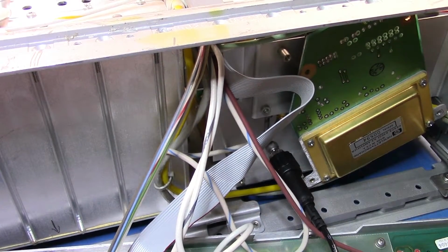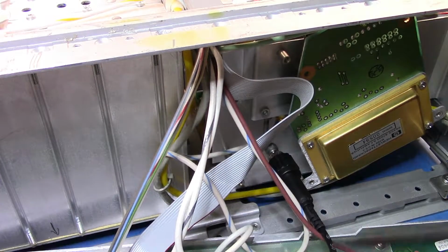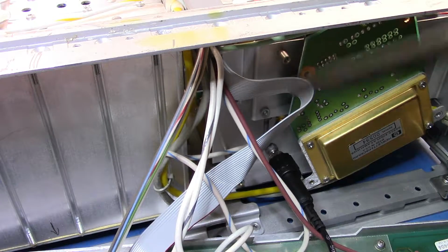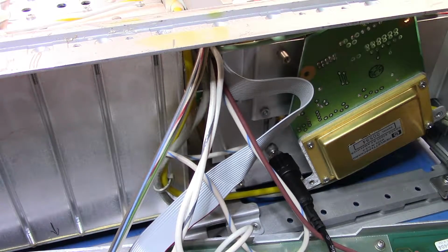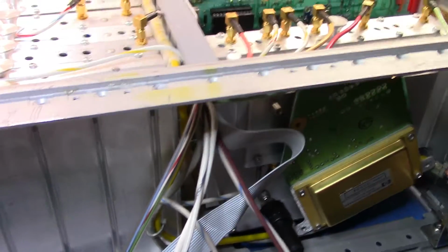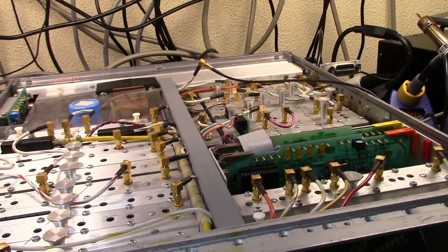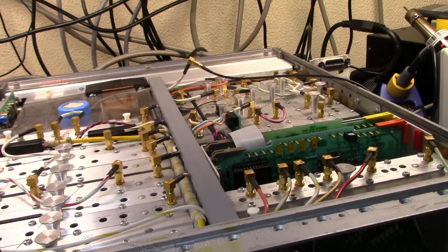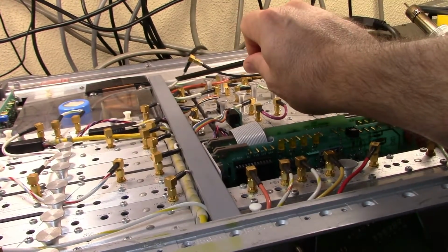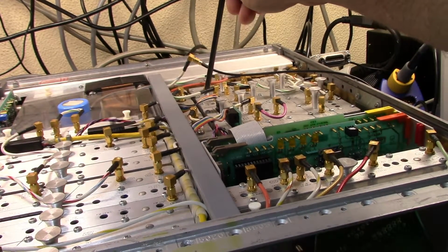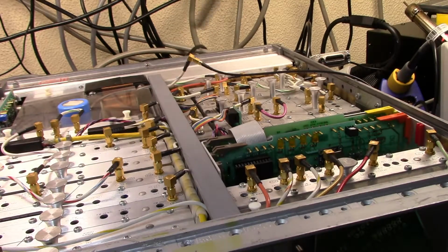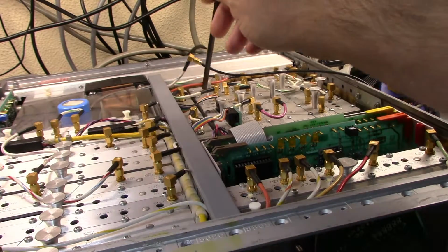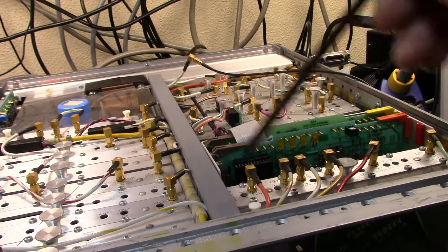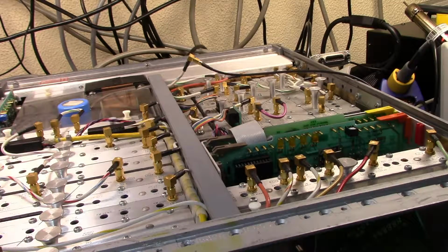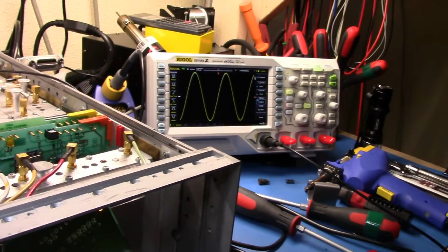Okay, so now I have the signal generator connected up to the hard line that goes into the system, and that line goes in and becomes a bit of coax that, and if we undo my mount here, we'll be able to see it, that goes up to the back here, and it's this guy here, and it goes into the A16 RF detector assembly. And so what I've done now is I've just fed the same signal in through that line over to my scope here.